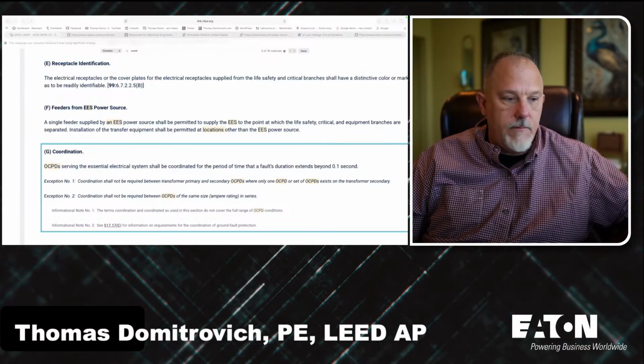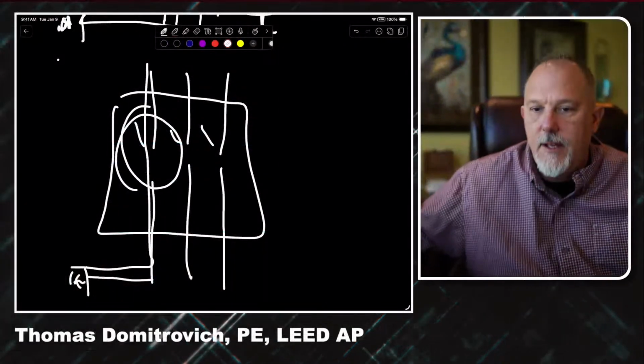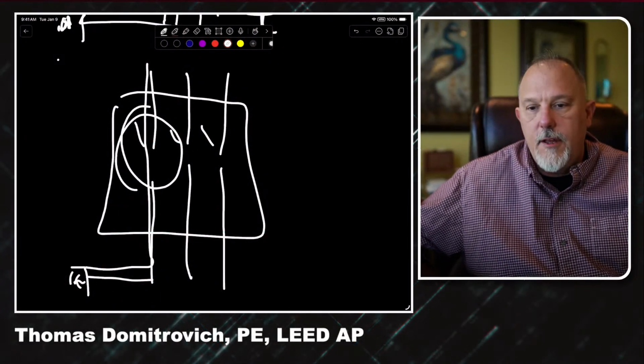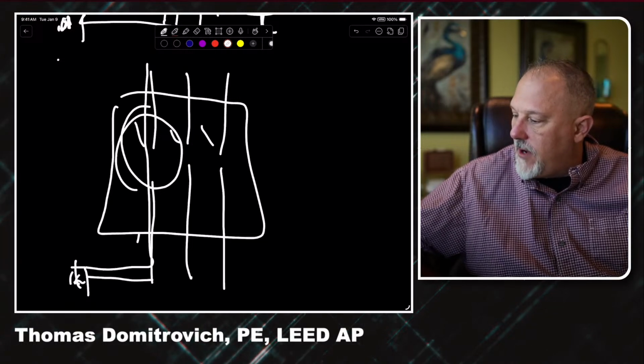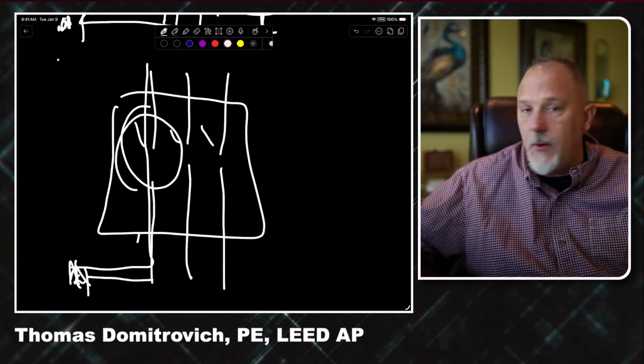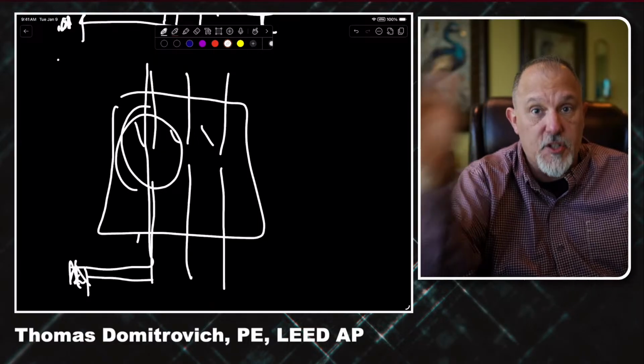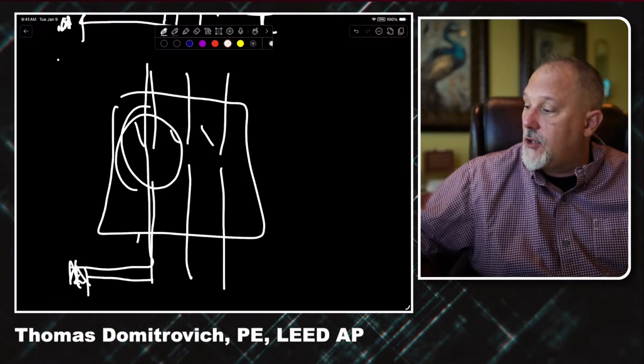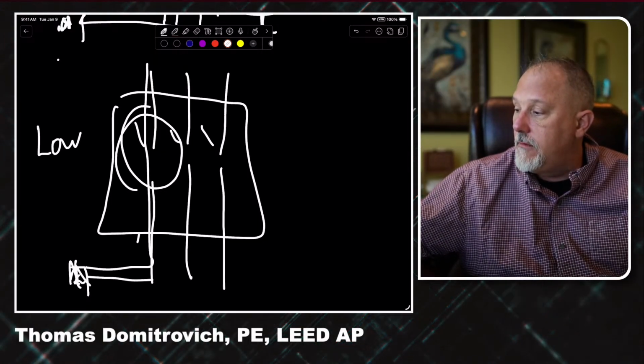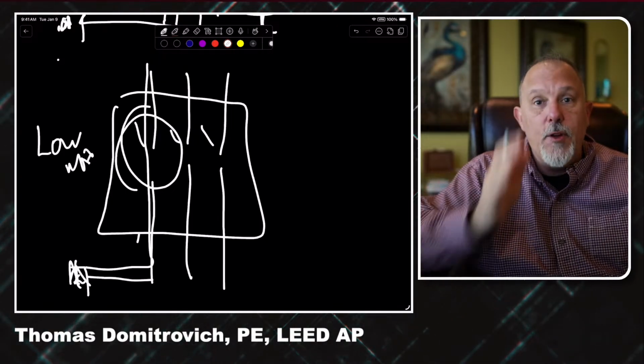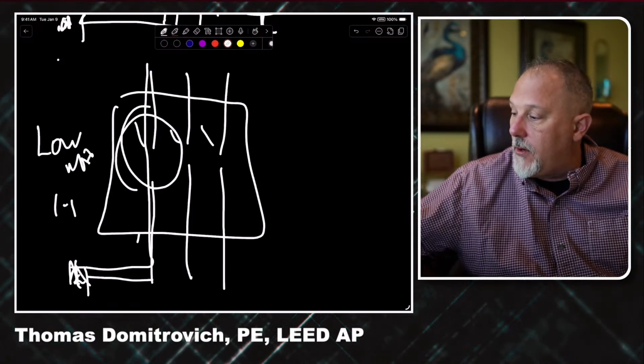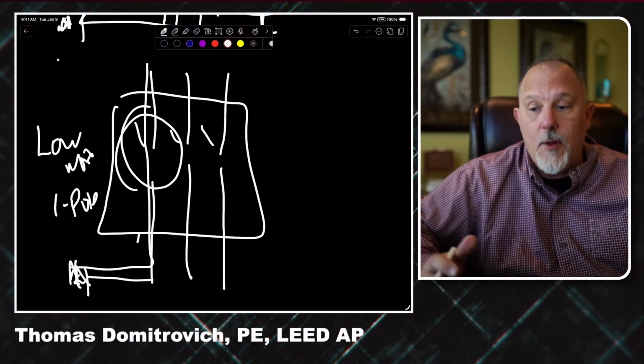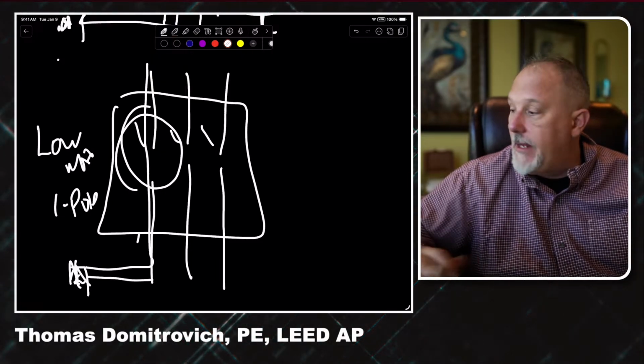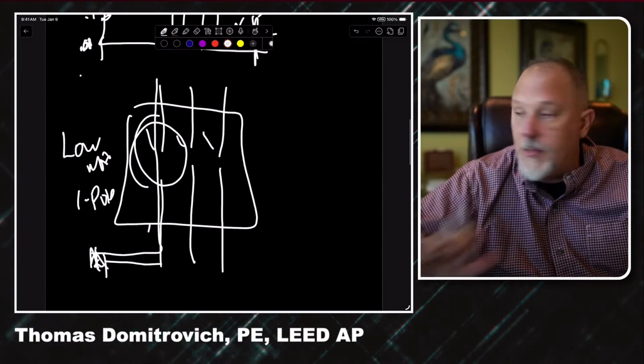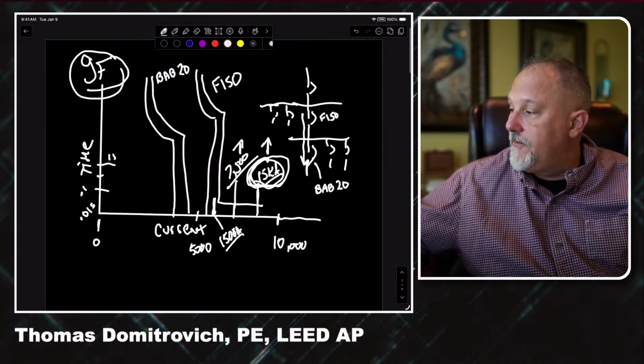And that pole, if I have 3 poles and I have a ground fault current flowing through one of those poles, that one pole is going to respond to that current. It's going to be a lower magnitude, but it will be seen in one pole. That one pole will have to respond. All right? So that's an important piece of this puzzle.